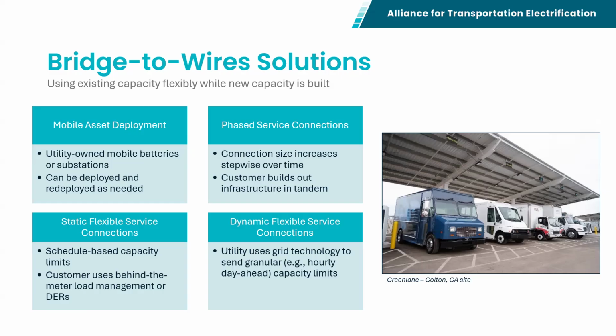Increasingly, utilities are getting authorization to purchase mobile batteries or substations that can be plugged into the grid to support a particular site until the new capacity is built. One advantage is that after use, they can be redeployed elsewhere. This mobile asset deployment idea is gaining some prominence, but it has limitations: it's pretty capital intensive, and it's not always easy to deploy, decommission, and redeploy batteries on the grid. Still, we've had some utilities get approval to do this.